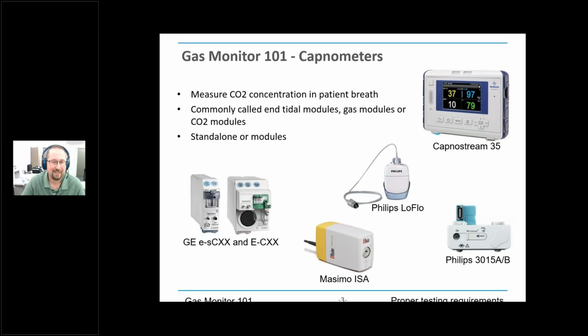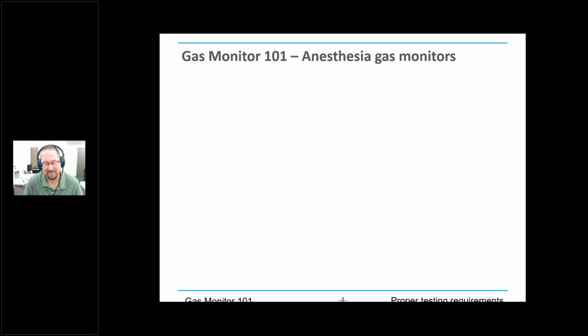There's a different class of gas monitors, which are the anesthesia gas monitors. They work on the same basic principle, but an anesthesia monitor measures not only CO2, but also oxygen, nitrous oxide, which is laughing gas, and anesthetic agent. And most anesthesia monitors will also produce a waveform for each of those gases. We'll talk a little bit about that in a minute.